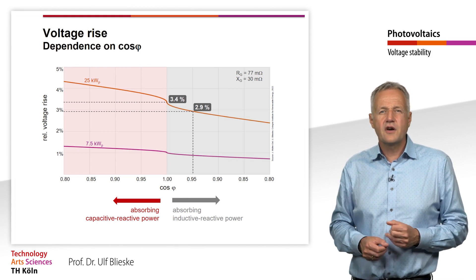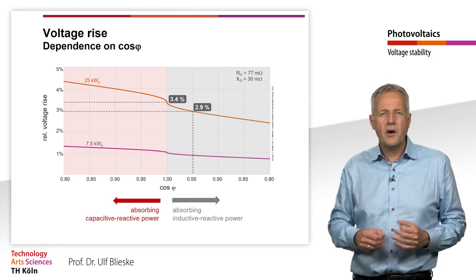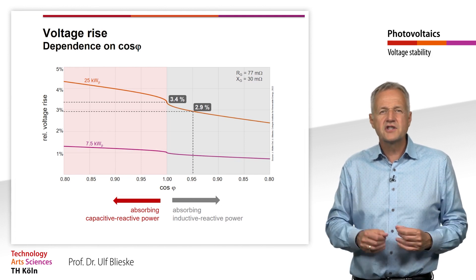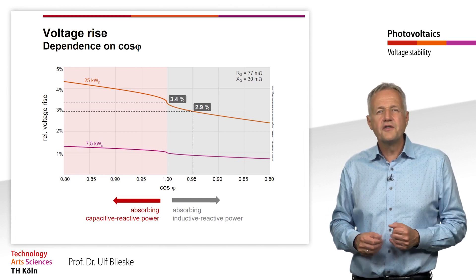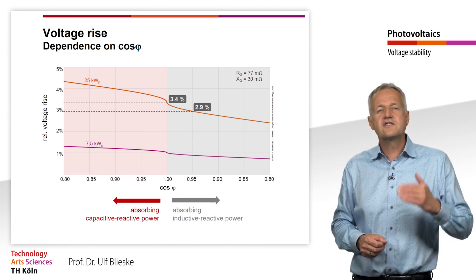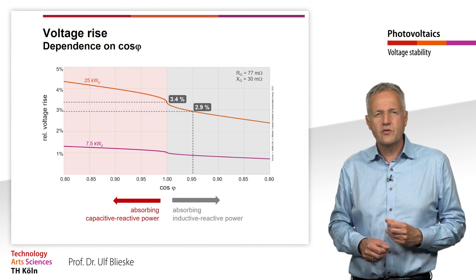If the inverter of the plant feeds in with a power factor of 1, thus without a phase shift between current and voltage, the result is a voltage increase of 3.4%. This is just above the limit provided by the grid operator.